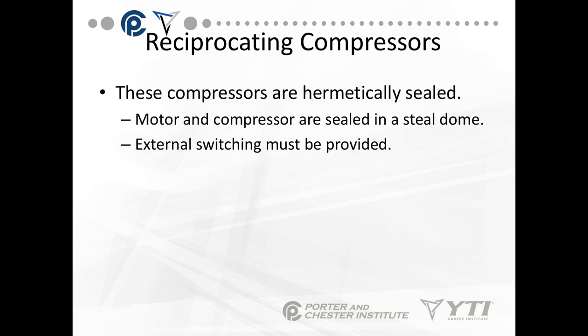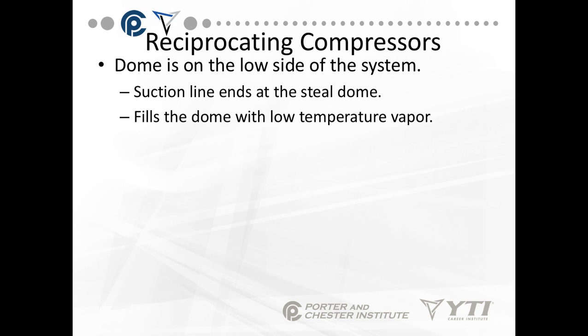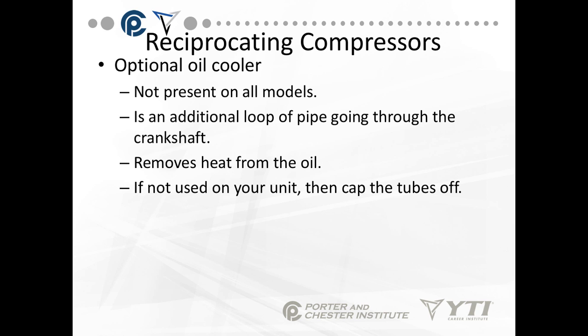These compressors are hermetically sealed — the motor and compressor are sealed into a steel dome. External switching must be provided. The dome is on the low side of the system; the suction line ends at the steel dome, filling it with low-temperature vapor. There's sometimes an optional oil cooler — we take the discharge line, loop it back through the crankcase, and that removes heat from the oil and helps cool the system.